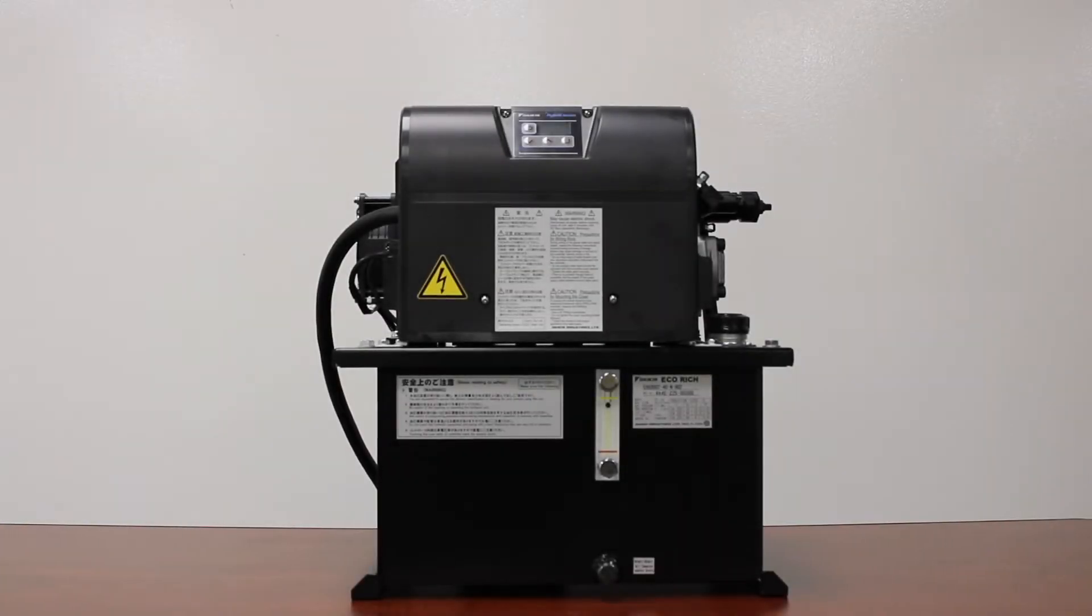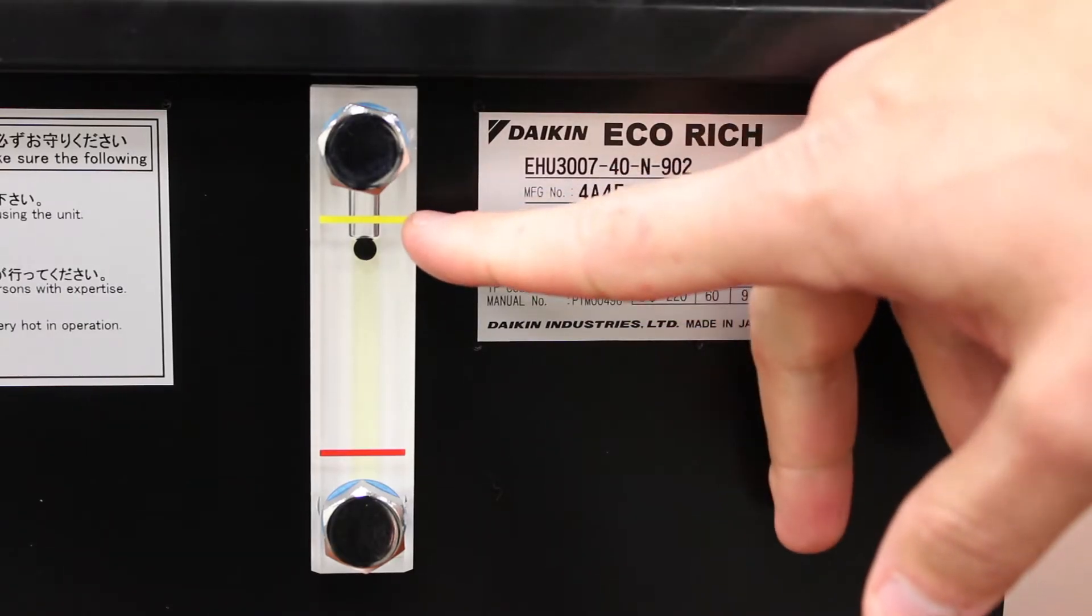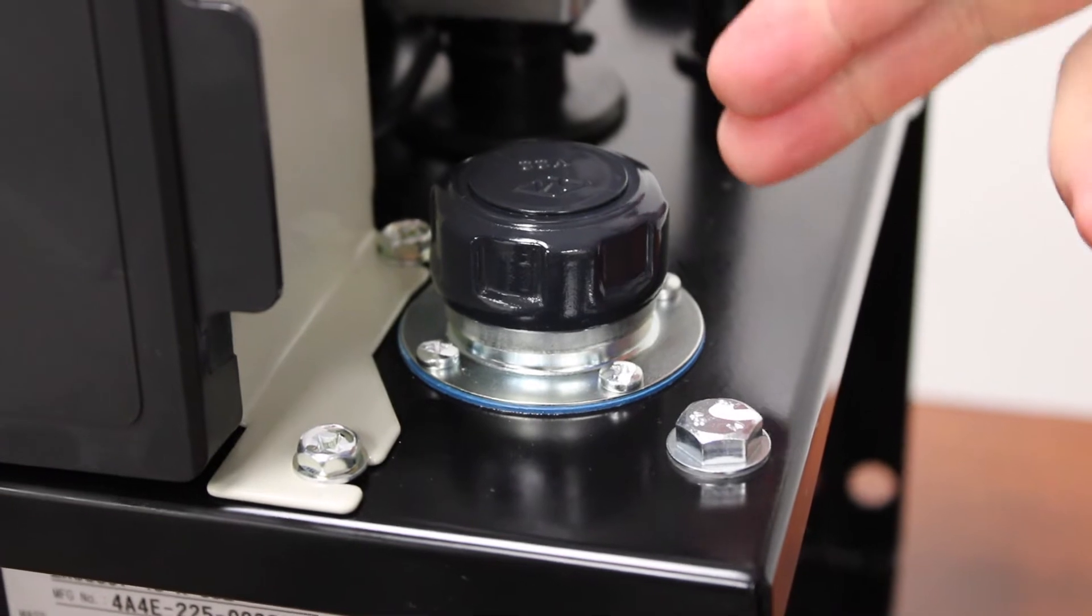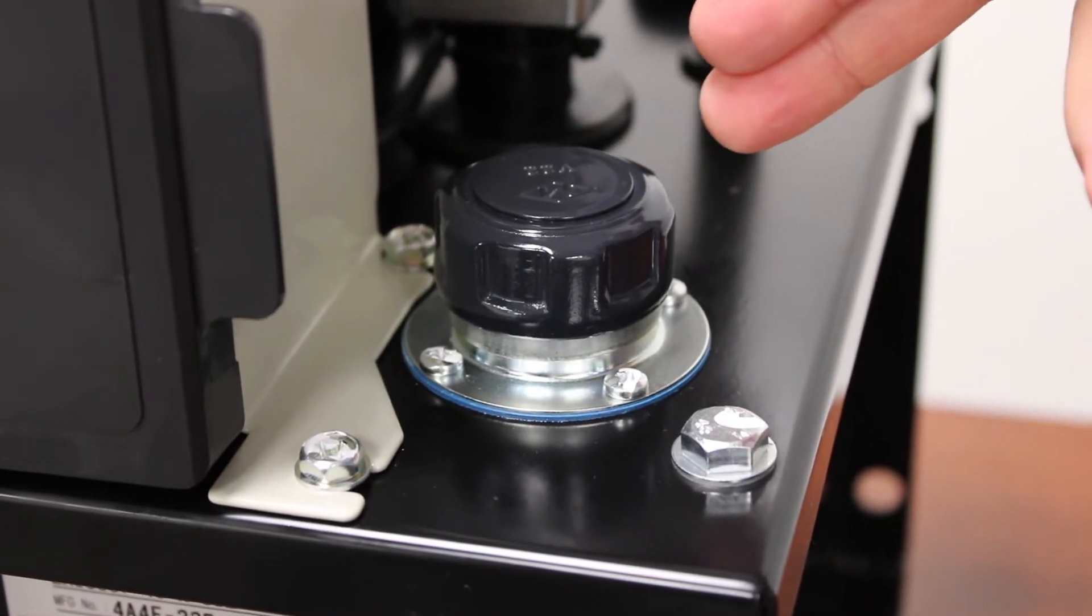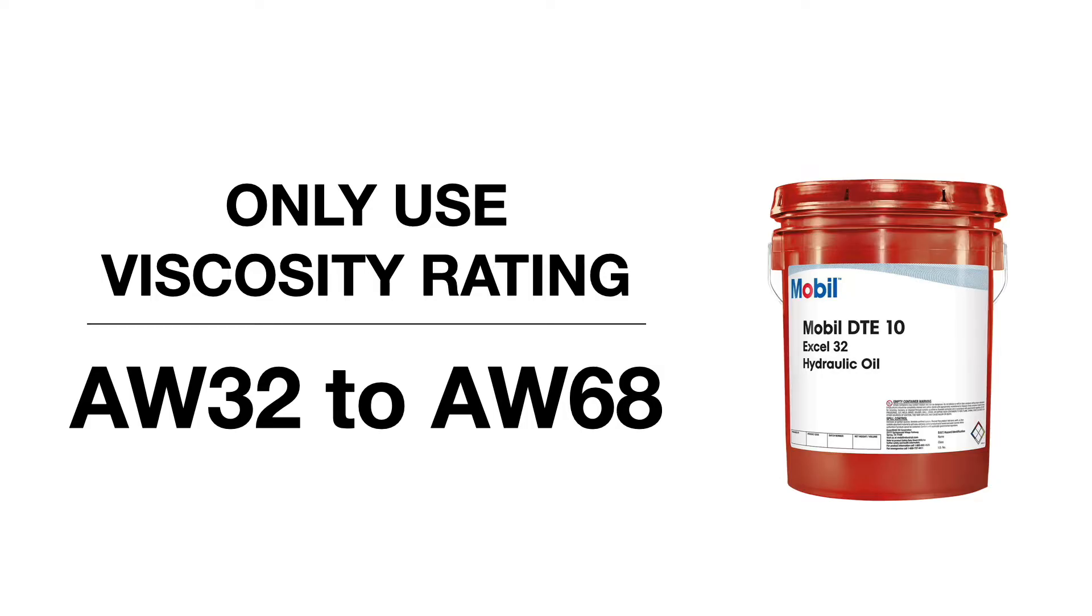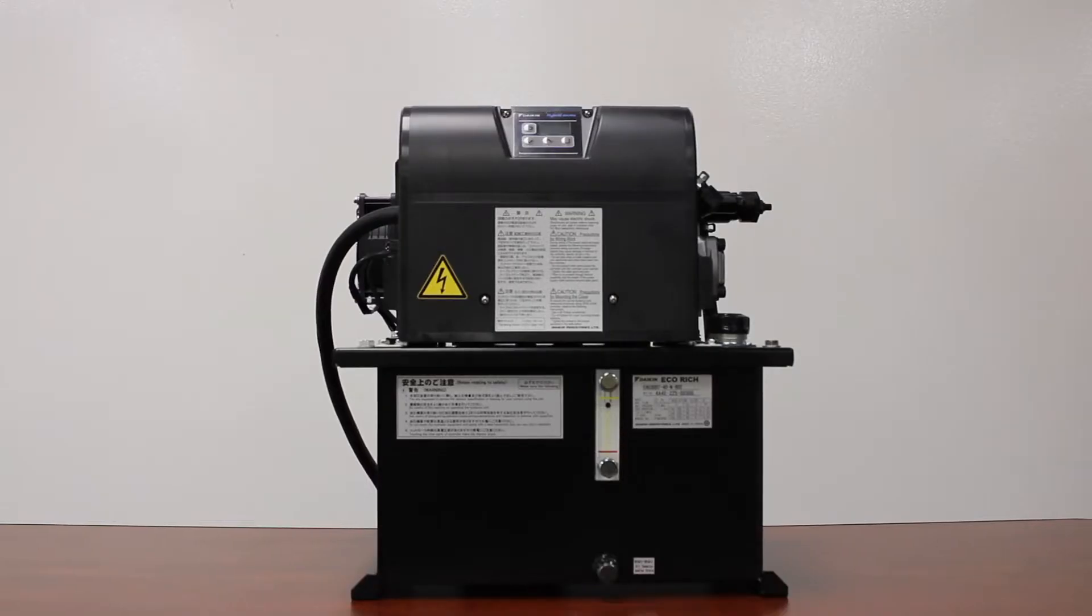To start off out of the box, you're going to want to fill the tank with oil. We can fill it up to here on the sight gauge. Your fill cap for the tank is right here on the front right corner. Any weight oil from an AW32 to an AW68 is acceptable.